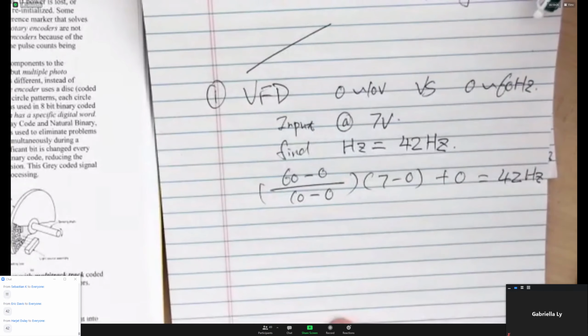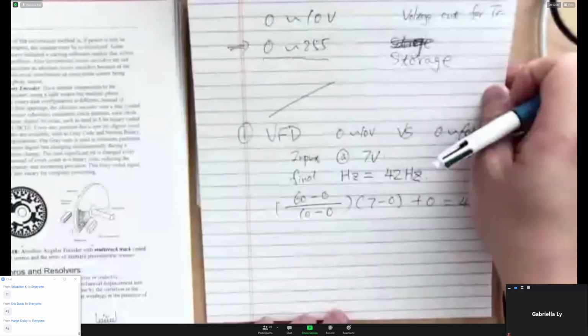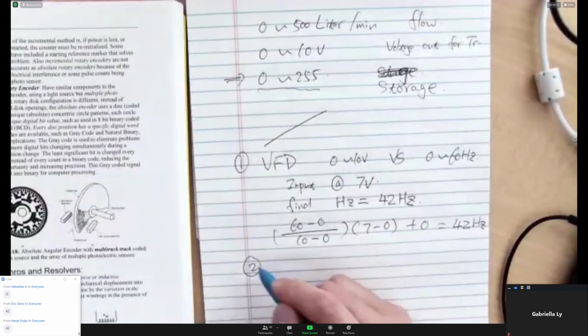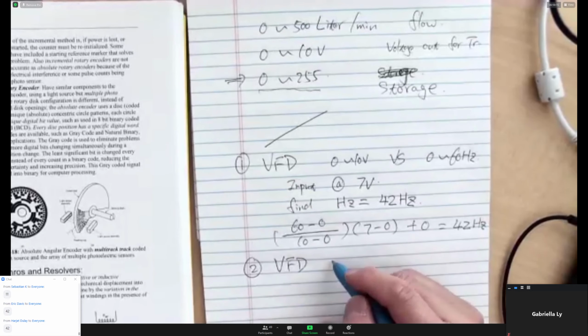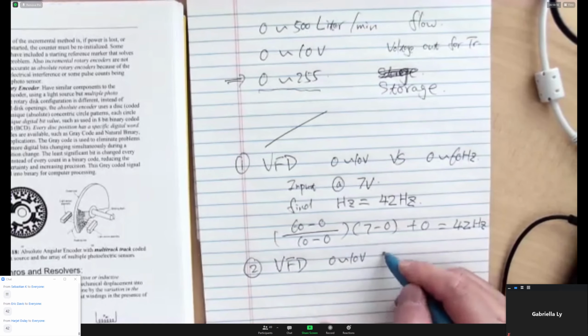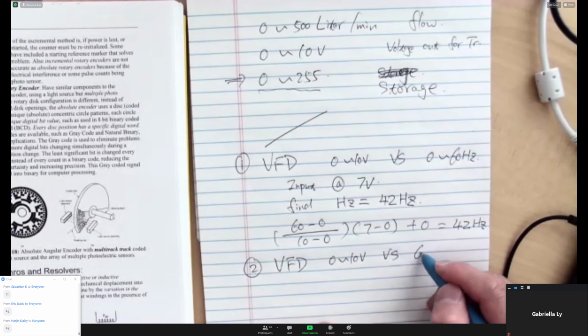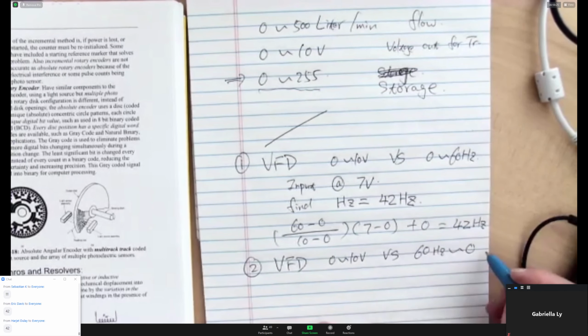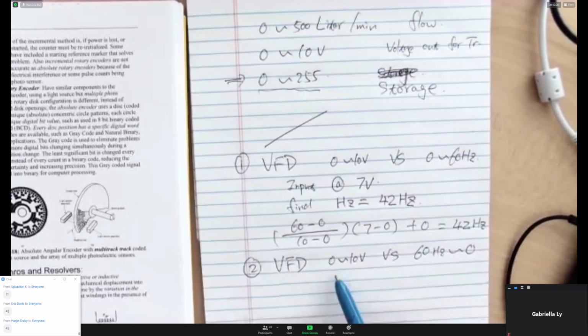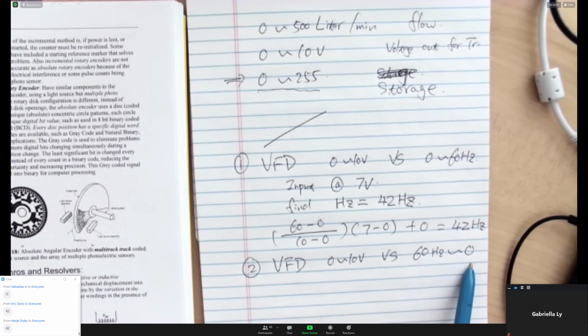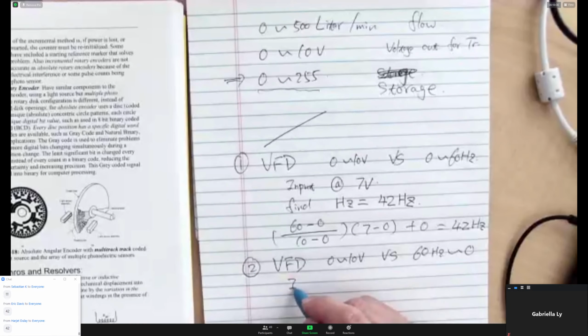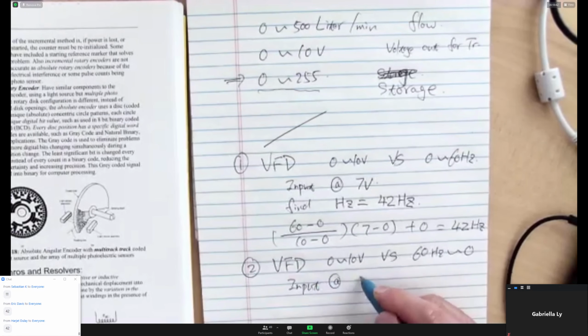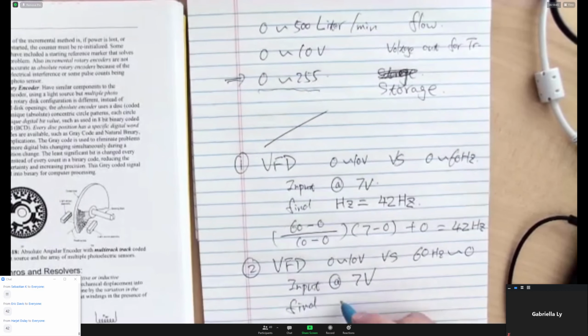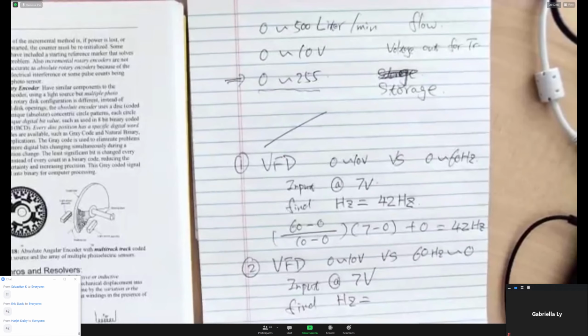But you could totally encounter a different question. A VFD using 0 to 10 volts versus 60 hertz to 0. So now 0 volts gives you 60 hertz, and 10 volts gives you 0 hertz. Let's say my input is at 7 volts. Can you find out what the frequency is going to be?